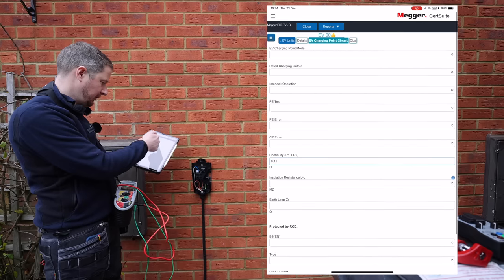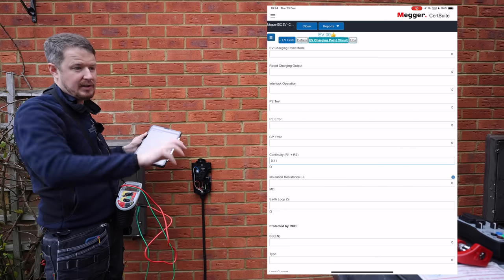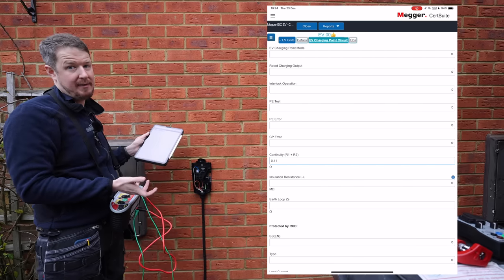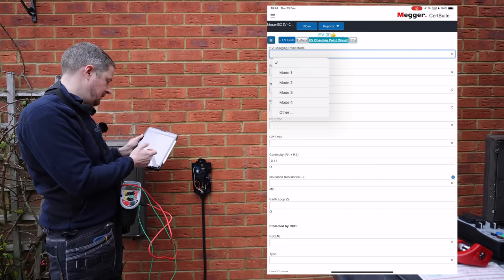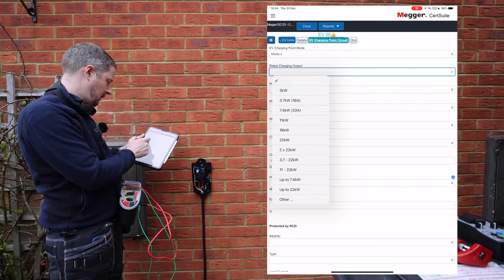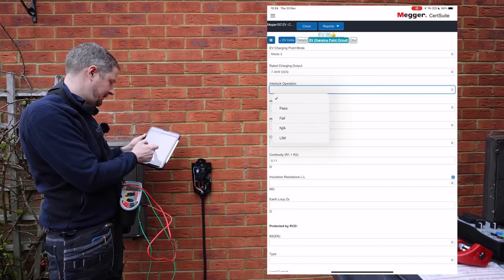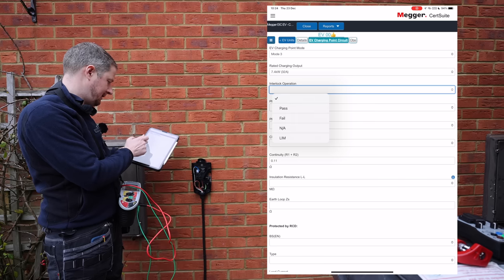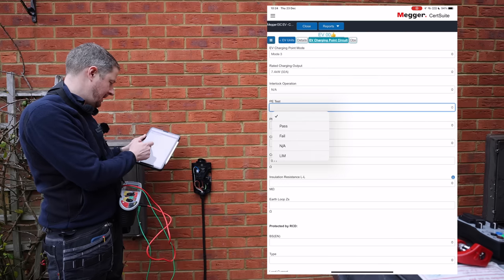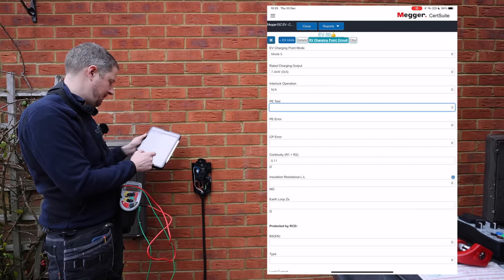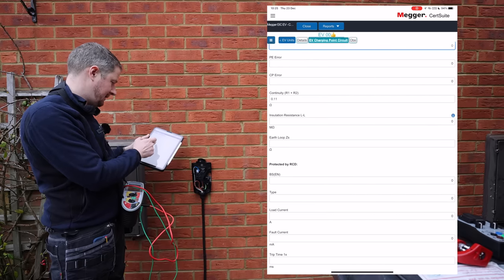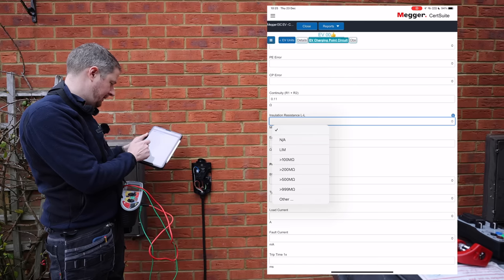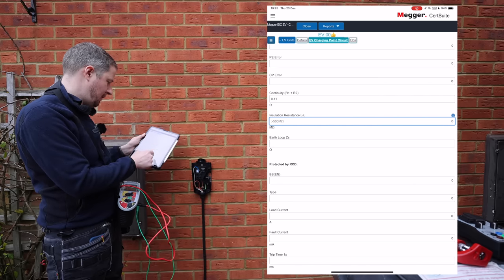But also then the EV charging point circuit, so this is where we'll input our R1 and R2 of 0.11. But it's also got the various functional tests for the charger that we're going to run through with our EVSE test unit. So that's really important too. So we've got, it's a mode three, it's got 7.4 kilowatts, interlock, doesn't have an interlock because it's not an untethered. PE test, we'll do all of that in a minute, the CP, PP, all that stuff.